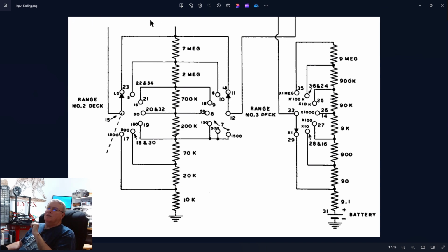You've got a bunch of switches up here that decide what to do with the incoming probes — which probe is coming in and where it should be routed to make sure it goes to the right place. For example, the AC signal isn't brought to this resistor array directly; it goes through a rectifier first, so it routes there before coming here. On the other hand, when DC comes in, it routes straight into this.